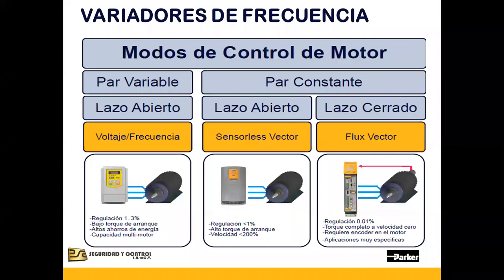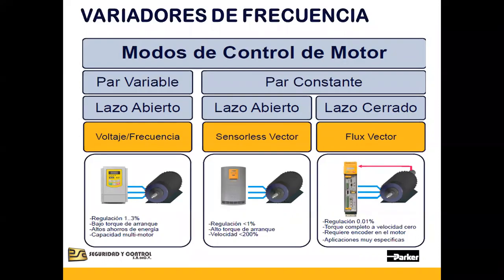El modo Volt-Hertz maneja una regulación o eficiencia entre el 1 y el 3% de la frecuencia que administra al motor. Maneja un bajo torque de arranque y tiene un altos ahorros de energía. Tiene la capacidad particular de manejar multimotor, es decir, que bajo un solo variador se puede manejar una gran cantidad de motores. Se puede manejar una sola señal de control y el voltaje del motor varía en relación proporcional con la frecuencia de la curva.